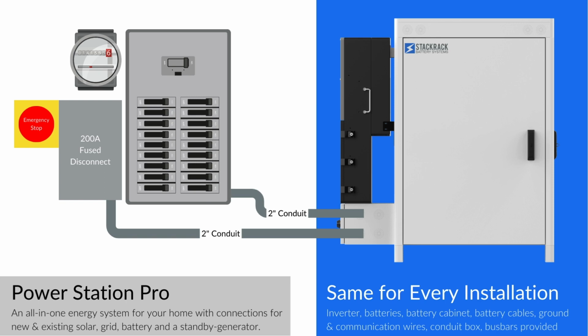So what that means from an installation standpoint is once you've installed Power Station Pro 1, 2, 3 times, you can become very familiar with the steps, and this can help really reduce installation time and complexity. Furthermore, we provide all battery cables, ground and communication cables, conduit box, inverter, hardware for this unit. And this unit can be placed on a concrete slab, on a generator pad. It takes up a very small footprint.